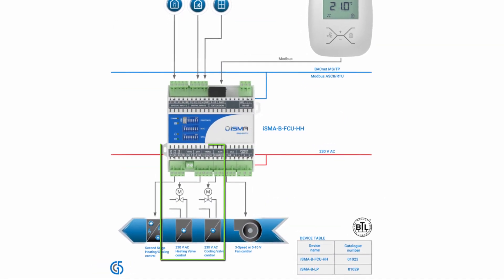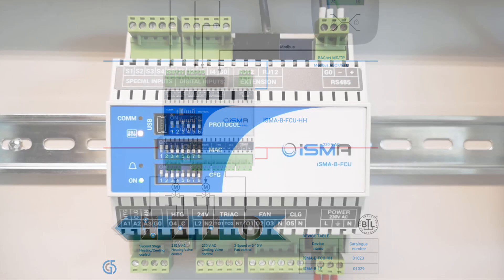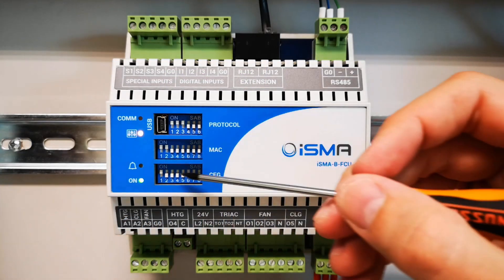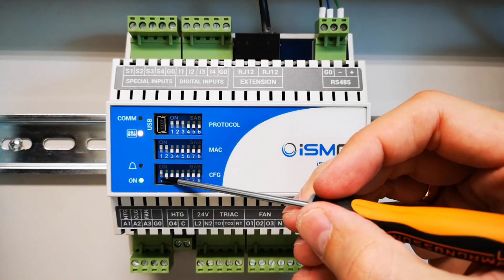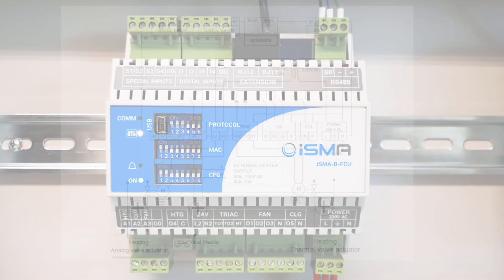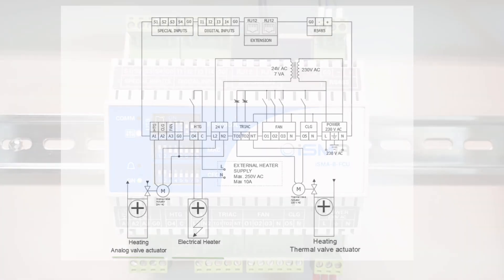In case of 4-pipe, both hot and chilled water are available to the FCU. The second configuring DIP switch selects if our fan coil unit controller will work with a single heating device (first stage only) or with two heating devices — a basic first stage and an additional second stage.